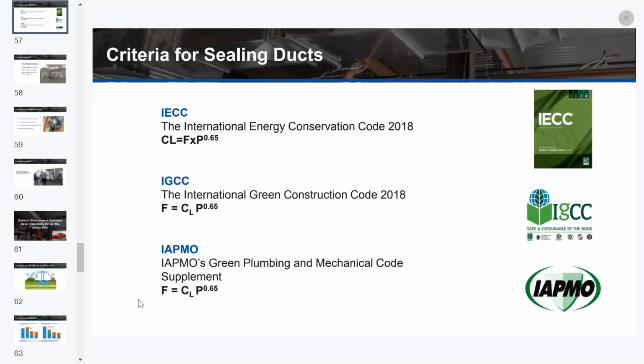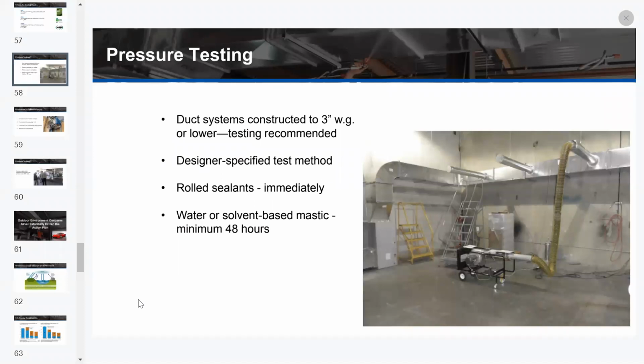So as we talked about, IECC, IGCC, and IAPMO all use similar equations and guidelines for testing. When you're doing a pressure test, you're going to do a leakage test for the duct system, typically constructed to 3 inches of water gauge or above. At 3 inches of water gauge or lower, typically not testing, but it's still recommended per the SMACNA guidelines. What we're seeing out in the industry is that you're testing everything. And if so, the designer must clearly designate in their documents the portion of the system to be tested, and they must specify the appropriate test methods.